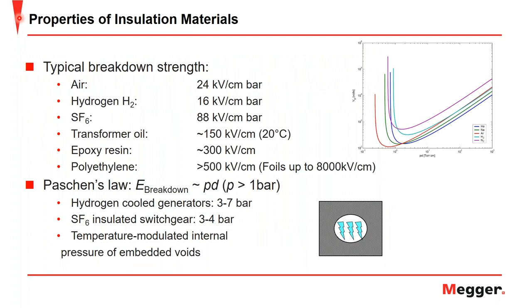So moving into some properties of insulating materials. Here we have a list of typical breakdown strengths of different insulating materials. The first one's air, which we had previously discussed briefly. And air is 78% nitrogen, which I mentioned earlier. And nitrogen is an electropositive gas, which makes it a poor insulator due to its availability of free electrons. But other gases, such as hydrogen or SF6, can be really good insulators when used in compressed forms, such as GIS or GIL. For instance, the breakdown strength of SF6 at 4 bar is roughly 3 times higher than at 1 bar.